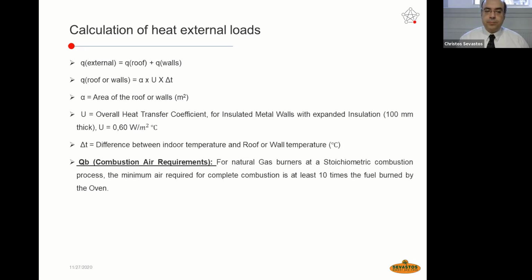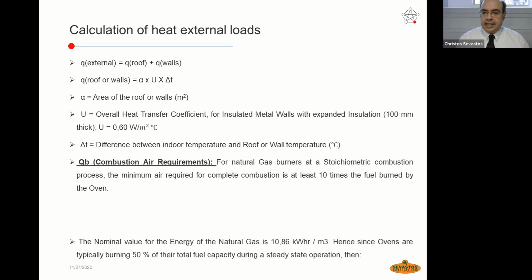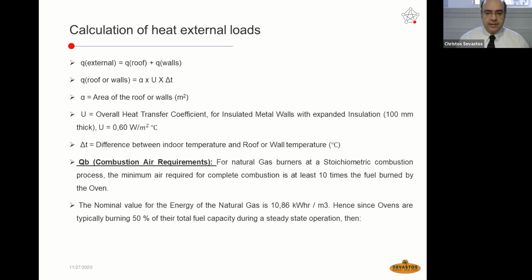Combustion air requirements, the QB. In the previous slides, we have seen the QB, the combustion air requirement, in situations where burners draw air from a dedicated air supply with individual flow of air. This QB factor could be 0, but in most cases the burners take the air from the environment. For natural gas burners at a stoichiometric combustion process, the minimum air required for complete combustion is 10 times the fuel burned by the oven.